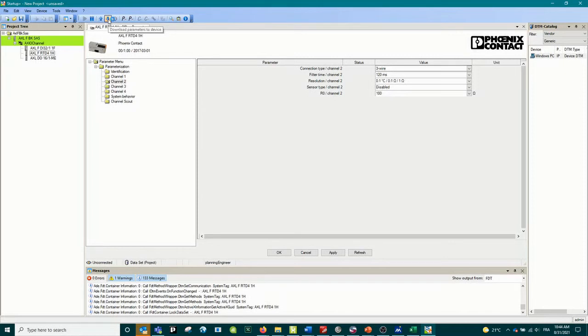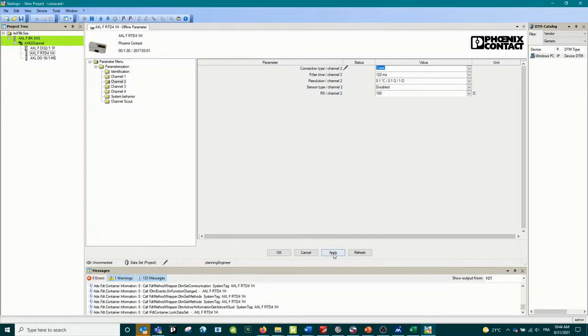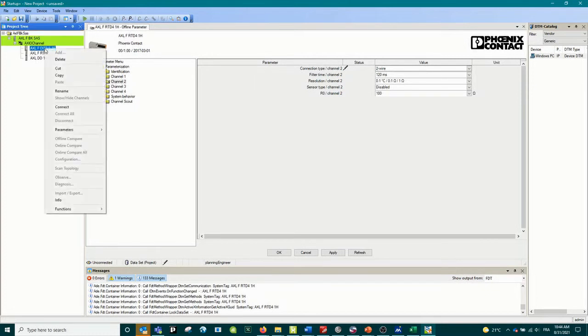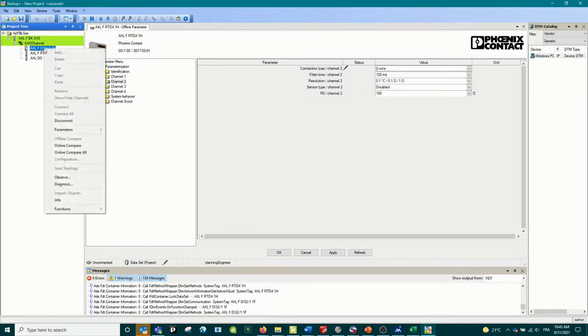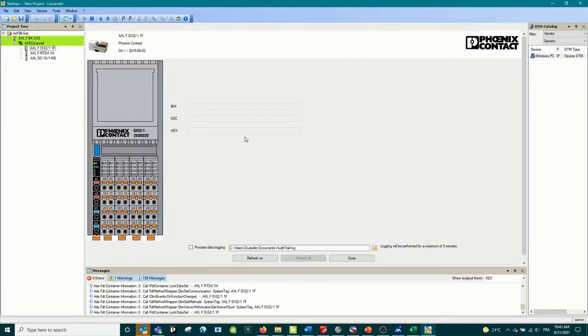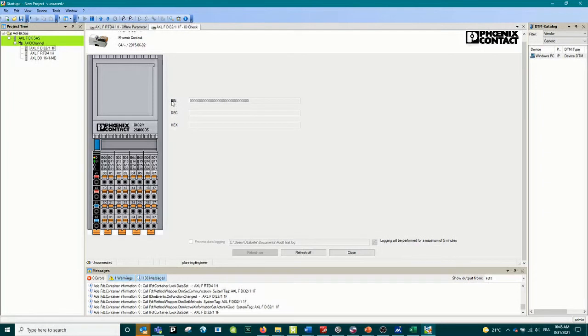Let's say everything is done - you don't need to press apply because each time you are changing something it's going to ask you to apply first. After everything is configured we are able to go online and do the IO check, so I just got to press go online with the 32 input and I'm going to right-click, function IO check. So IO check with a digital input - I'm just going to press refresh so it's scanning right now. It's going to show you the value in binary, bit by bit, decimal and hexadecimal. When everything is ready all lights over here will go white.